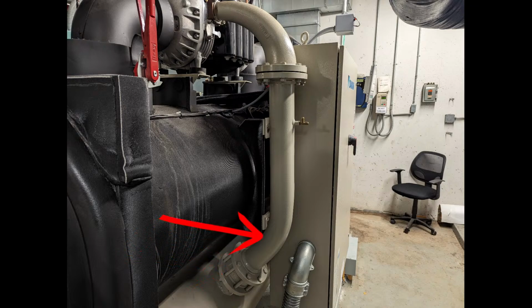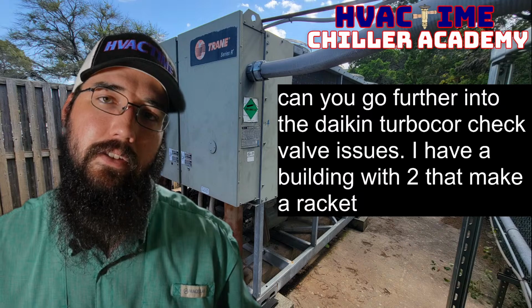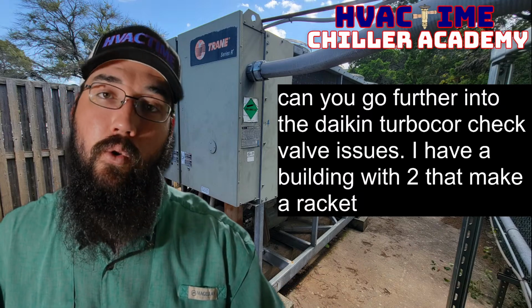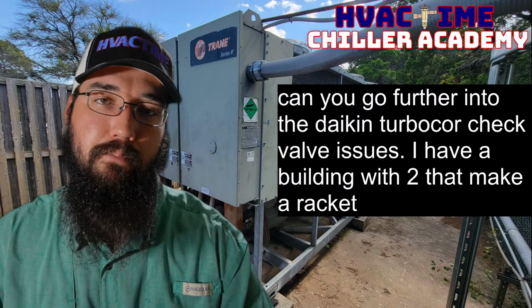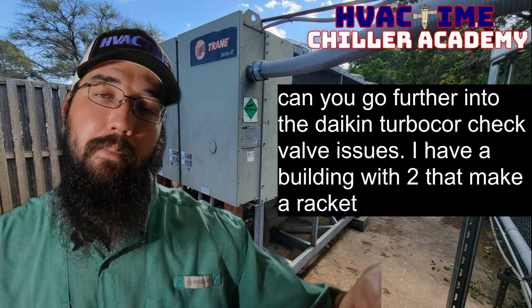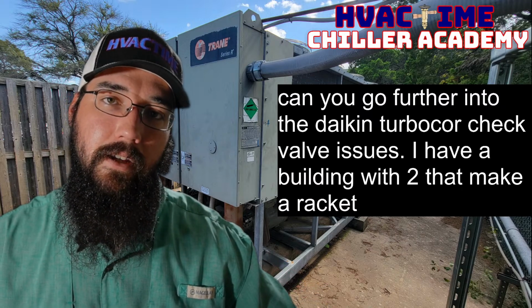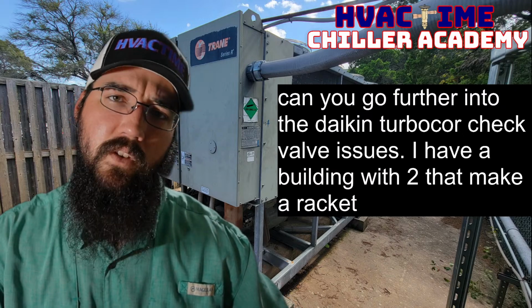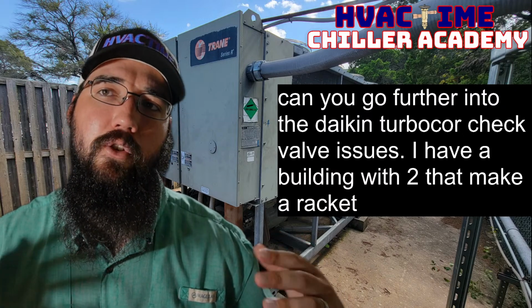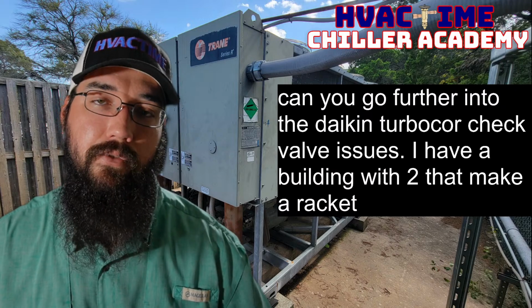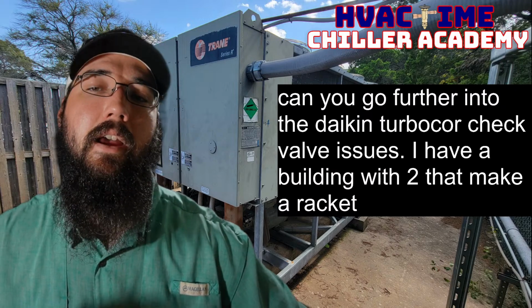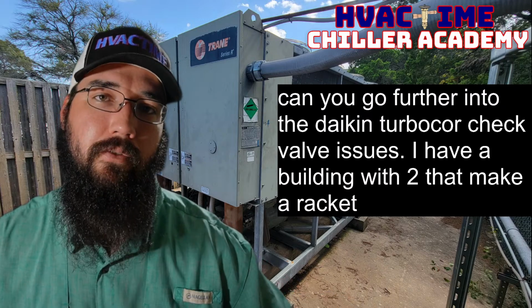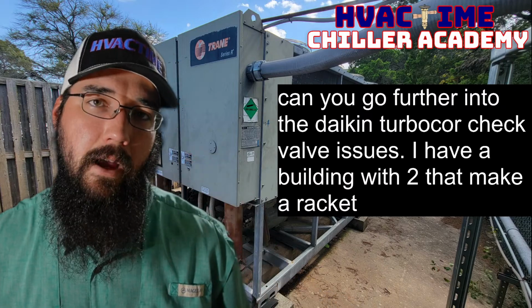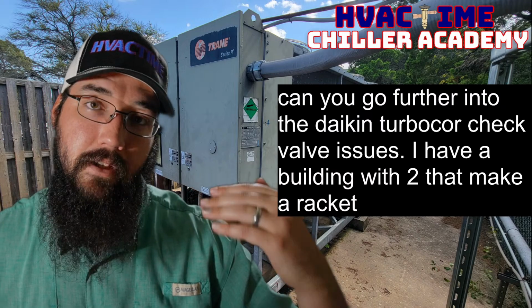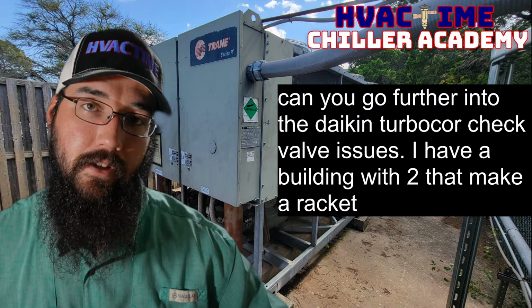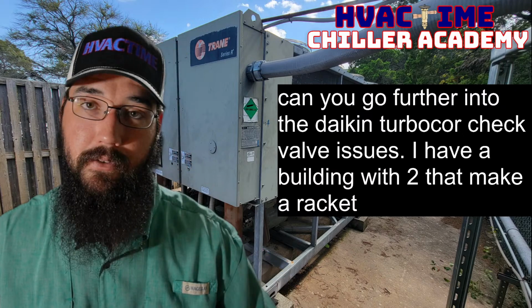Now, Daikin made retrofit kits that you could put into older machines, and you would basically just have to put in a tap on the heat exchanger and the pipe. You could install the valve assembly, and you could also upgrade the discharge valve that was in there at the time. And you could do this whole upgrade kit to prevent the failures, because a couple of things were happening with the failures. Either they were completely shattering and then sending shrapnel into the condenser. That was one failure that was happening.